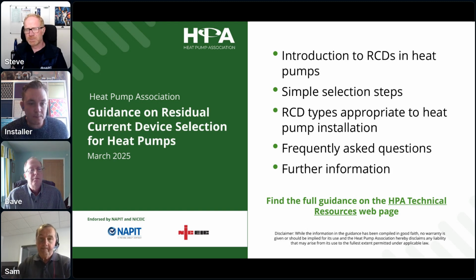That's a good question, because sometimes we consider RCDs just for the protection of people when we think about prevention of an electric shock. And you could argue that that's the most common application and probably one of the most important applications to protect against electric shock. But there are times when we use RCDs, and they've been around for many, many years, that are used to protect equipment and maybe an electrical installation as a whole. So instead of being used for what we'd call additional protection, where they are to protect against electric shock harmful to people, they can also be used for fault protection and also fire protection. So, under certain fault conditions, the protective measure, we could have insulation faults, for instance, where we could have an RCD in place for that.